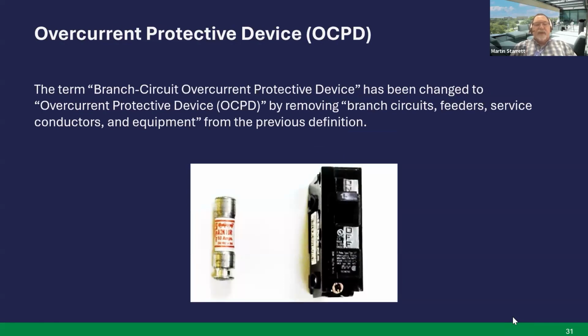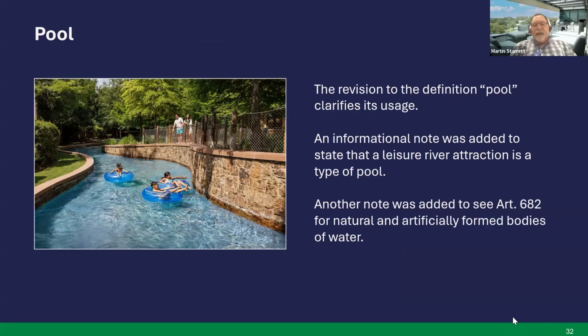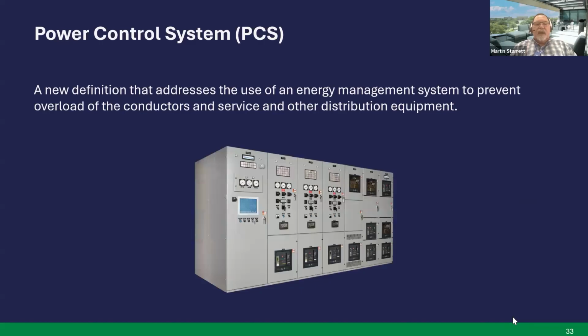Overcurrent protected device. The term branch circuit overcurrent protective device has been changed to strictly overcurrent protective device by removing branch circuits, feeders, service conductors, and equipment from the previous definition. Next slide. Pool. The revision to the definition of pool clarifies its uses. Also, an informational note was added to state that a leisure river attraction is a type of pool. Another informational note was added to see Article 682 for natural and artificially formed bodies of water. Next slide.